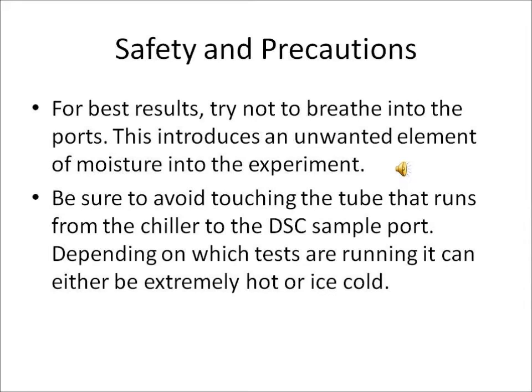For safety and precaution, try not to breathe into the ports. This introduces an unwanted element of moisture into the experiment. Be sure to avoid touching the tube that runs from the chiller to the DSC sample port. Depending on which tests are running, it can be either extremely hot or ice cold.